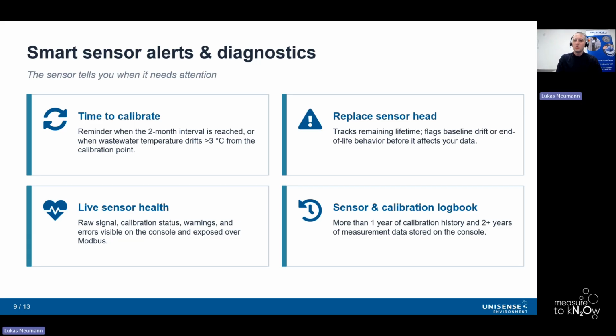It will alert you when it's time to replace the sensor head. It tracks the remaining lifetime. As before, we have the guaranteed 4 months, but it typically lasts 6+ months. And it will flag you when there's a baseline drift or end-of-life signals before it affects your data. Then more broadly, the sensor will keep track of the sensor health, so raw signal, calibration status, warnings, errors, all exposed over Modbus, and you could pull this into your SCADA and trigger alerts there as well.